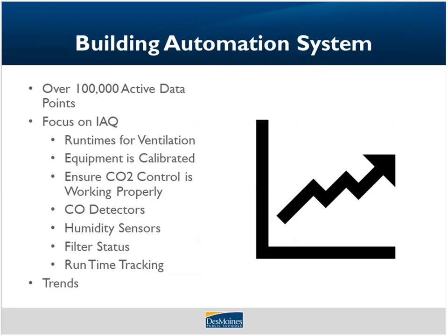Our building automation system is very robust and helps us manage our equipment efficiently. It allows us to schedule our occupied times, which helps prevent unnecessary equipment from running. And programming within the BAS staggers the startup of equipment to minimize our peak demand during the winter months. We don't have everything starting up at once.